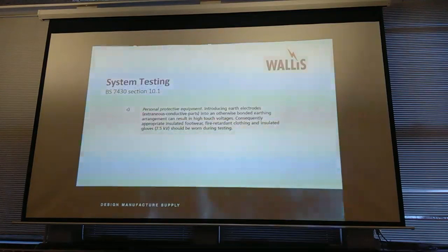So, you know, it's things like that that people need to be a little bit more aware of. Disconnecting earths isn't the done thing anymore. There is technology out there, there is test equipment out there that, if designed correctly up front, you never ever need to disconnect an earth ever again. The way we do things is we put an earth rod in, we put a cable from the earth rod, the cable runs through the pit, that is then welded to the earth system. All you do then, pop the lid off the earth pit, you put the clamp meter around it, read the reading, done. That's it. No disconnection, no messing about, everybody's safe.